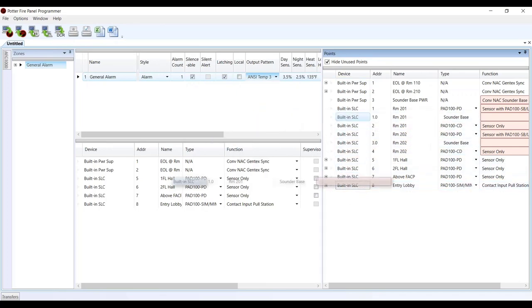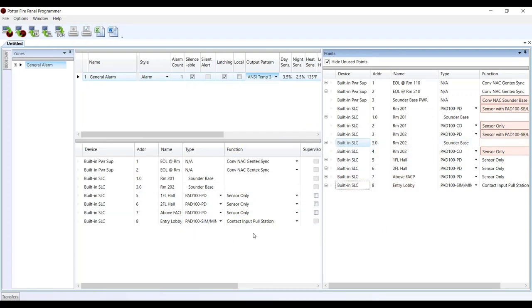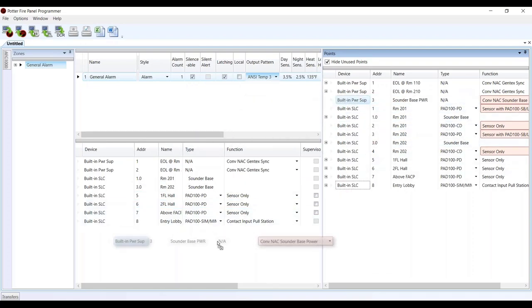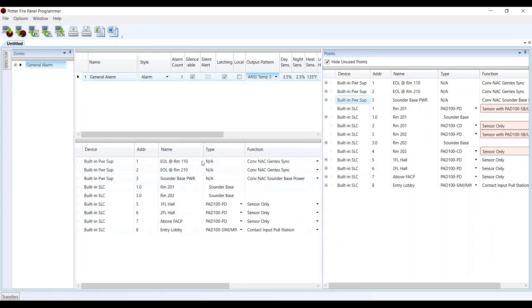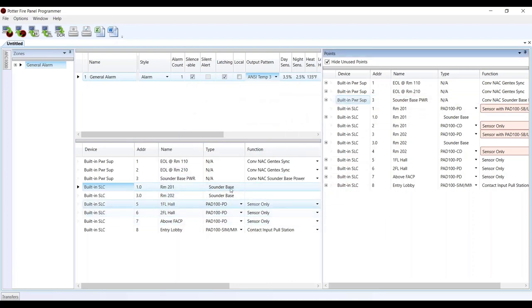I'll grab the sounder base from room 201 and from room 202. The last thing — and I think this is probably the part that gets missed the most — wherever you put your sounder bases, you have to put your sounder base power in there also. If you forget that step, it's not going to do the pattern you're looking for. If you leave out the sounder base power and set off the sounder base, it would just be constant — there would be no temporal 3. Always remember: wherever your sounder base goes, sounder base power goes with it.